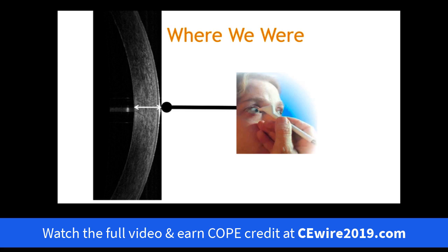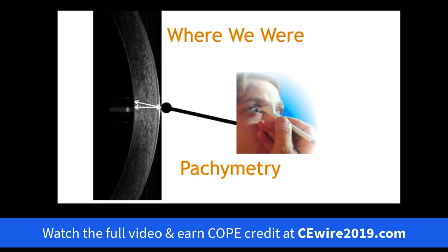When we look at traditional ultrasound pachymetry, if the probe is appropriately placed and perfectly perpendicular to the cornea, we get extremely accurate results. But if the ultrasound probe is tilted or turned, the differential between the anterior and posterior surface of the cornea is artificially lengthened. That's why using ultrasound pachymetry, you'd typically take eight or ten readings and select the three consistent thinnest readings — because thicker readings were likely from a probe placed at an angle rather than perfectly perpendicular.